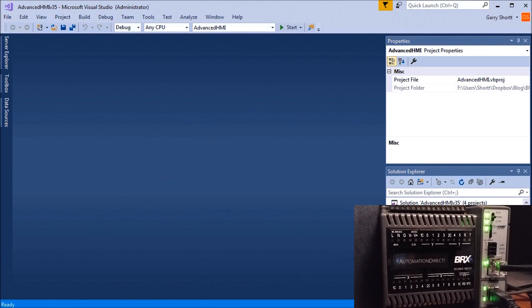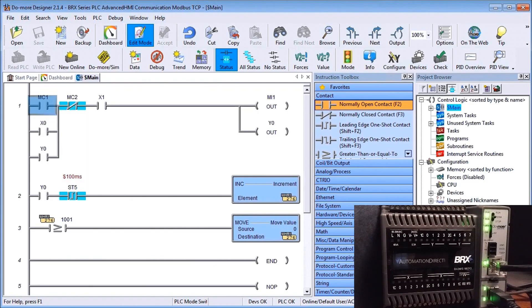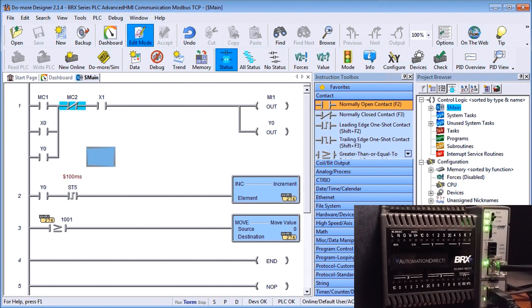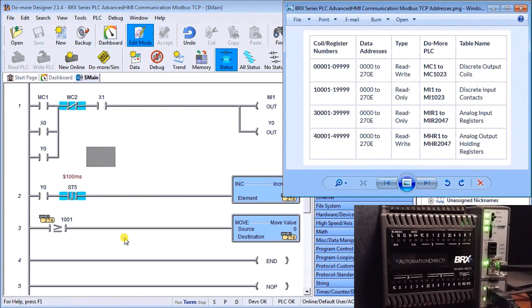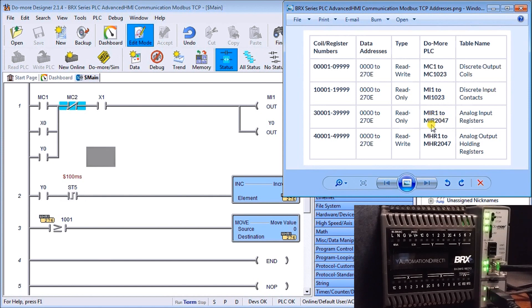Going back to the Do More program: during the Modbus TCP protocol, you want to identify where the addresses are in your program by looking at the address map. Everything on Modbus TCP through Ethernet goes through Modbus registers. We have Modbus coils 1 to 1023 as discrete output coils, discrete input coils at MI1 to MI1023, analog input registers MIR1 to MIR2047, and Modbus holding registers 1 to 2047.